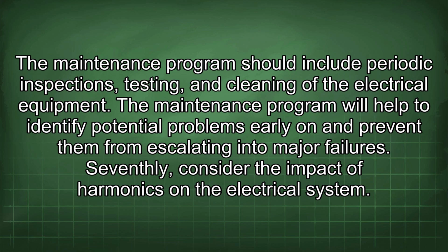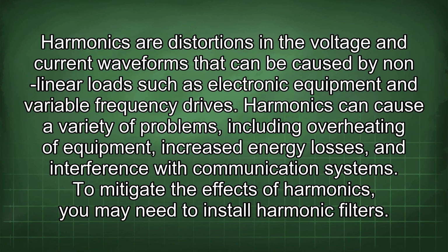Seventhly, consider the impact of harmonics on the electrical system. Harmonics are distortions in the voltage and current waveforms that can be caused by nonlinear loads such as electronic equipment and variable frequency drives. Harmonics can cause a variety of problems, including overheating of equipment, increased energy losses, and interference with communication systems. To mitigate the effects of harmonics, you may need to install harmonic filters.